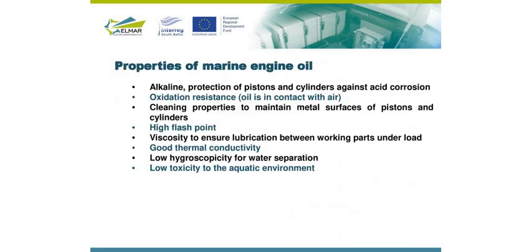It's also important to apply a good quality marine engine oil. The oil needs to meet many requirements: it needs to be alkaline, to provide protection of pistons and cylinders against acid corrosion. Oxidation resistance is also needed, as oil is in contact with air. The oil needs to have cleaning properties to maintain metal surfaces of piston and cylinders. It needs to have high flash points, viscosity to ensure lubrication between working parts under load, and also a good thermal conductivity. Another requirement is low hygroscopicity for water separation, and most important for us, low toxicity to the aquatic environment.